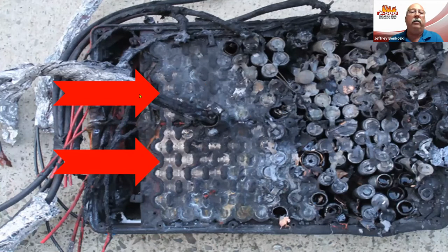Here's an example of a battery used in testing. It shows that, on the right, all these batteries went into thermal runaway and were failing. On the left, once the F500 solution was applied, they were able to extinguish and stop that thermal runaway, preventing more batteries from becoming involved.